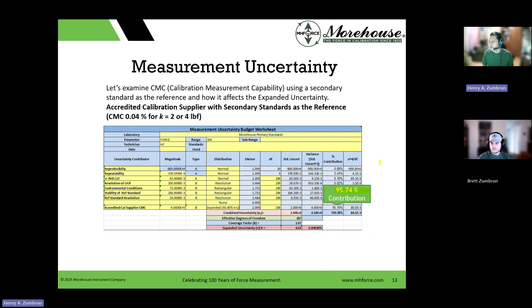Brett, what do you see as part of the contribution here? At least what I'm seeing right now, I see that large highlighted blurb. That's 95.74%. Yeah, so it was 14 and change percent, and all we did was change our reference standard, and now 95.74% of the overall uncertainty of calibrating this load cell, assuming nothing else changed on the load cell, it's still as repeatable and everything else, is 95.74.